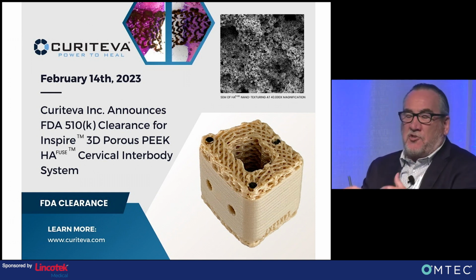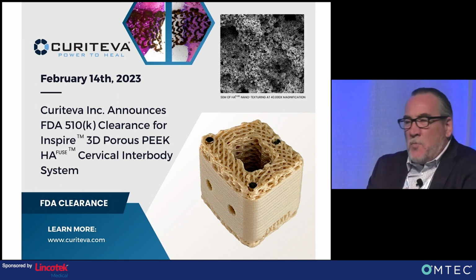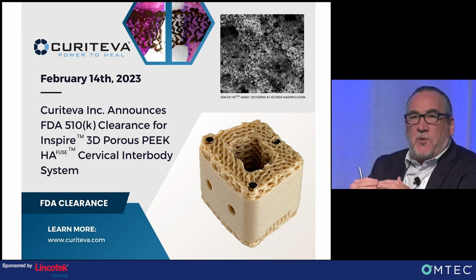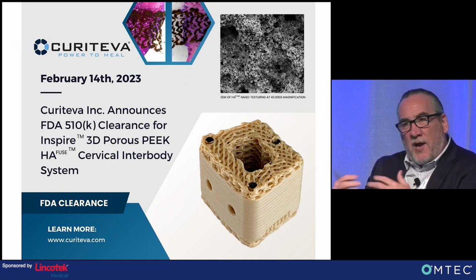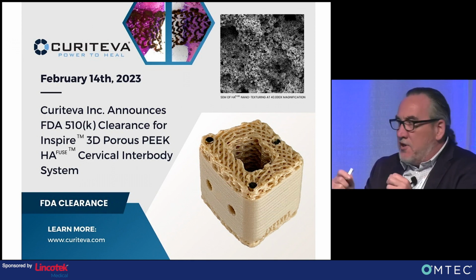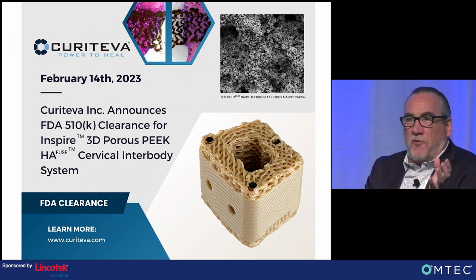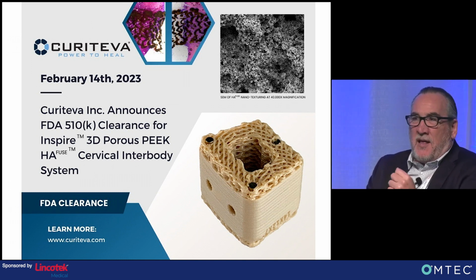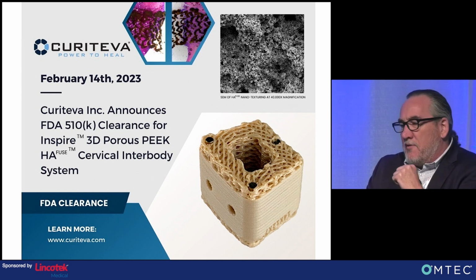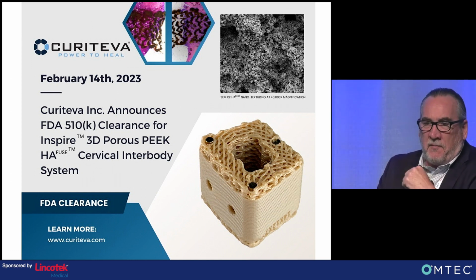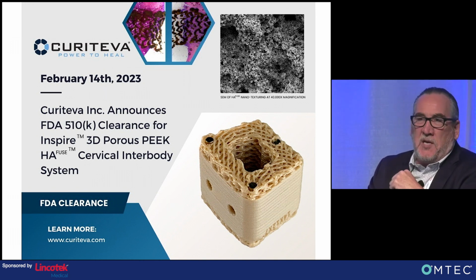So the strength values here, and I'll say one thing as a lead-in, the properties of PEEK are very dependent, as I said, on temperature, rate of extrusion, rate of deposition. Our ability to control, with the filament that we got from Evonik, going from the amorphous to the crystalline state is very key to making sure that the Z-layer bonding is there, where you're taking your footprint and then you're making a third dimension out of that. That's very instrumental in getting the strength values and the toughness values that we got. I'll just give you a quick example. The compressive strength, which is a very apparent test: if you take any of the cleared PEEK implants out, put it in a compressive ASTM 2077 compression test, they will fail usually under 8,000 newtons.